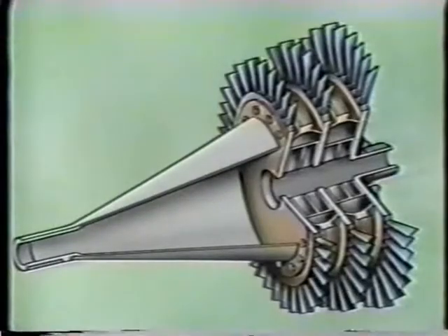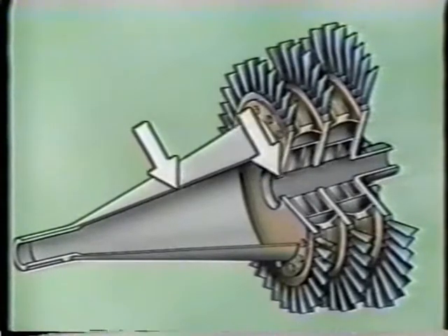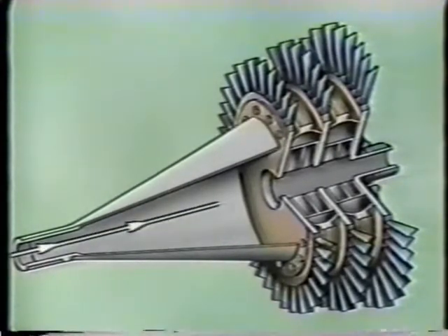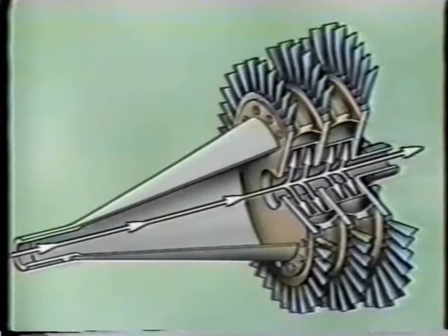New super alloys and protective ceramic coatings have improved the turbine blade's ability to withstand high temperatures. Some experimental turbine blades are completely ceramic, making them even more heat resistant. Compressor bleed air also can be used to cool down the turbine blades internally and protect them from heat. Many modern gas turbines have hollow shafts and discs. Cool compressor air is forced through the hollow shaft to cool the disc directly by convection. This also helps cool the blades.